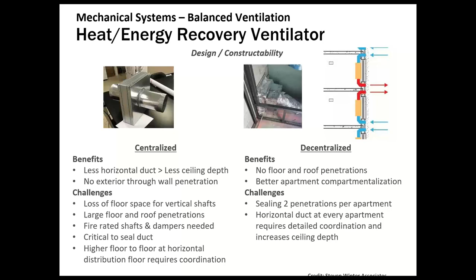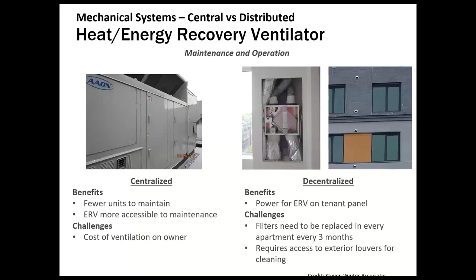It is also a benefit to maintenance and operation to have a simpler centralized type system with fewer units to maintain that is certainly more accessible to the maintenance staff. But of course, that also does put the cost of ventilation on the owner with a centralized system. Whereas with the decentralized systems, the power is all on the tenant's panel, so that can be considered a bonus, but filters need to be changed every 3 months, and access to these louvers should be maintained and considered because maintenance will be required at some point.